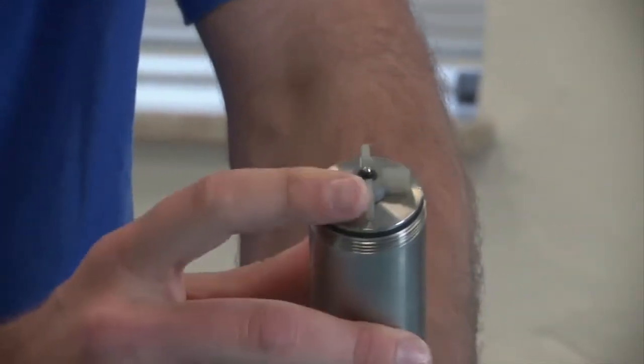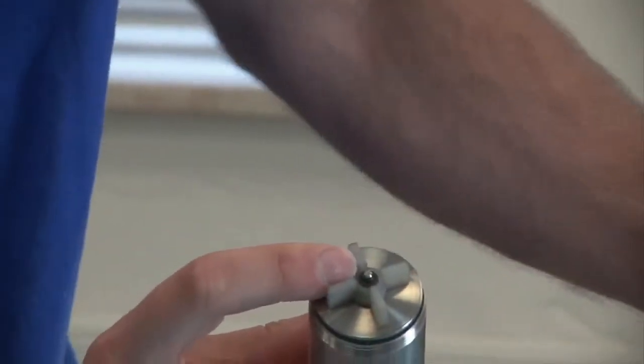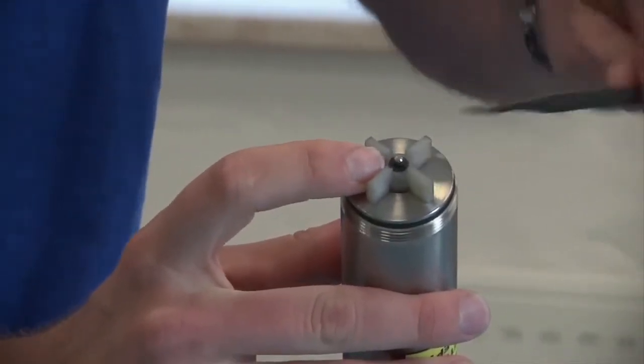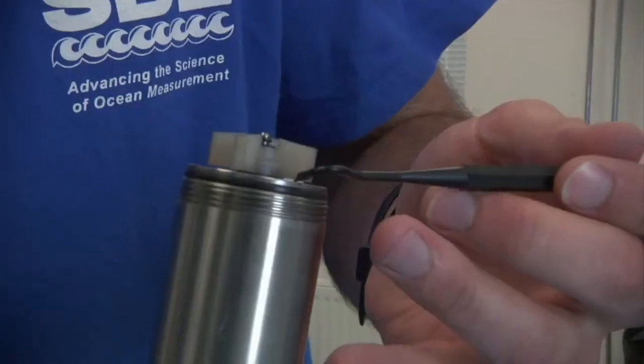You also want to check that there is a thrust washer and o-ring affixed to the top of the impeller. And then you want to check to make sure that there is about a millimeter gap between the impeller and the housing of the pump.